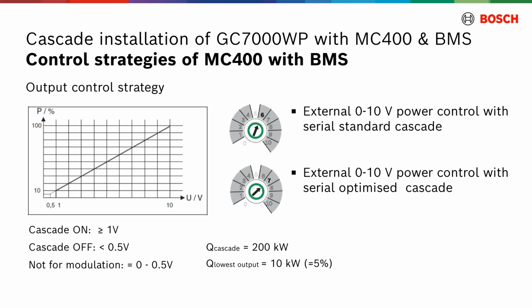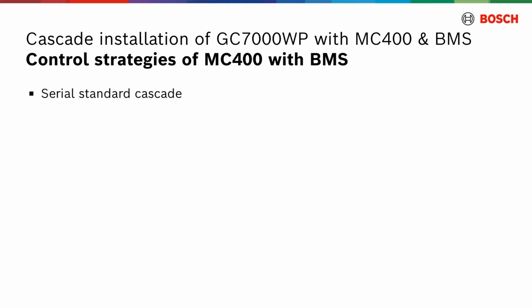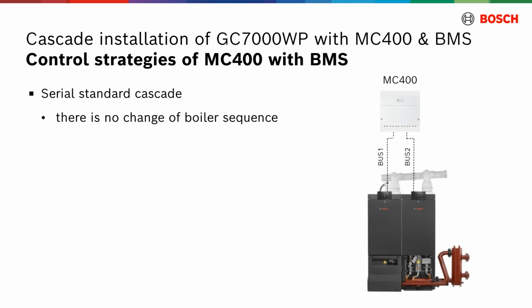And what is the difference between serial standard and serial optimized Cascade strategy? Serial standard Cascade. There is no change of boiler sequence. The connected heat generators are switched on and off according to the wiring. The boiler at bus 1 terminal starts first, then the boiler at bus 2 terminal follows. When deactivating, this sequence is reversed.